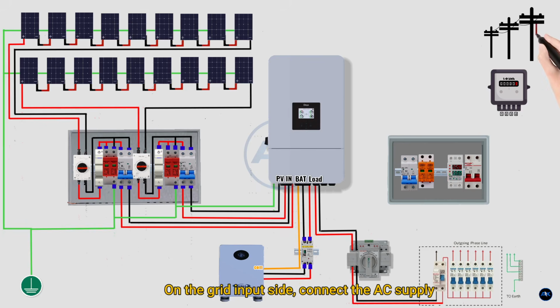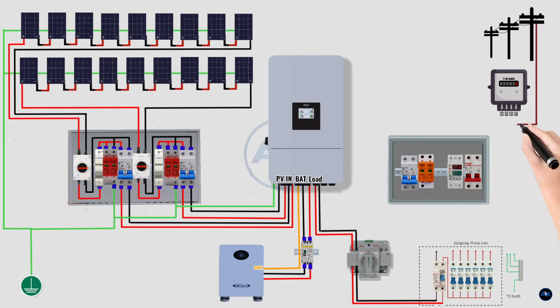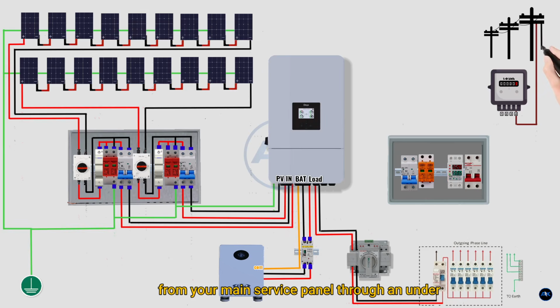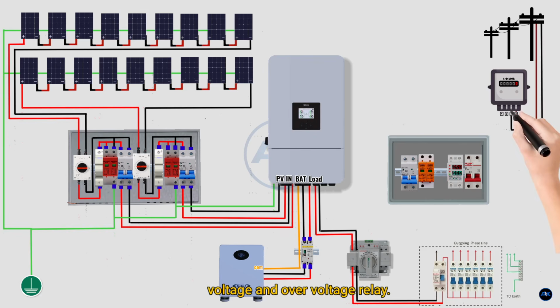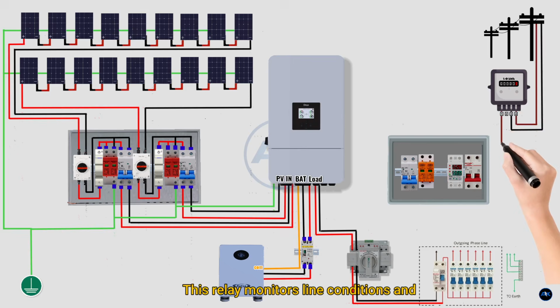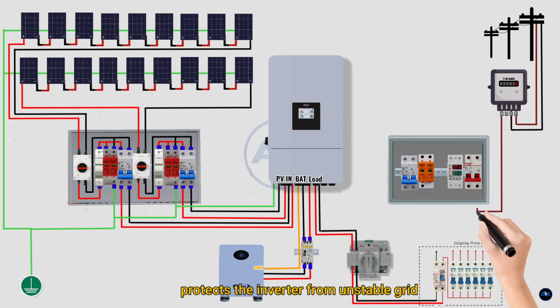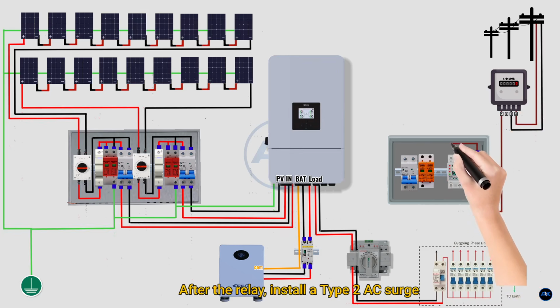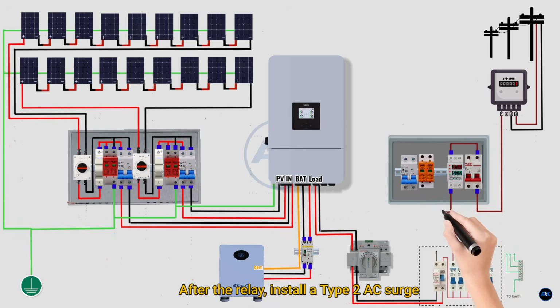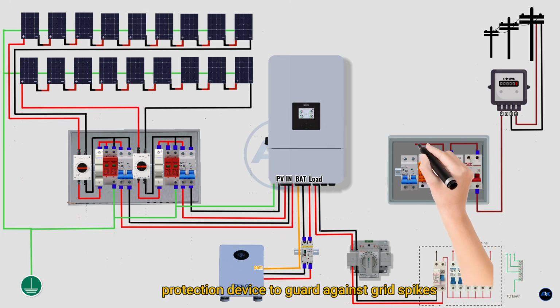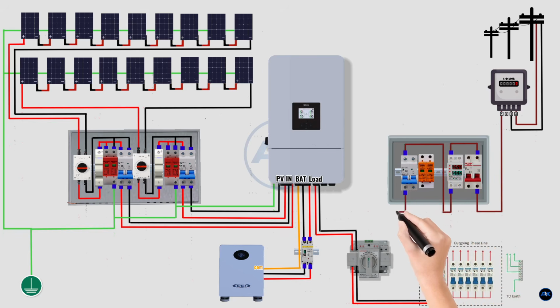On the grid input side, connect the AC supply from your main service panel through an under-voltage and over-voltage relay. This relay monitors line conditions and protects the inverter from unstable grid voltage. After the relay, install a Type 2 AC surge protection device to guard against grid spikes and lightning events.